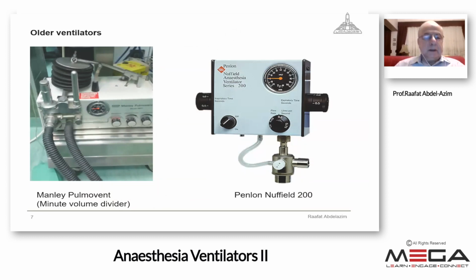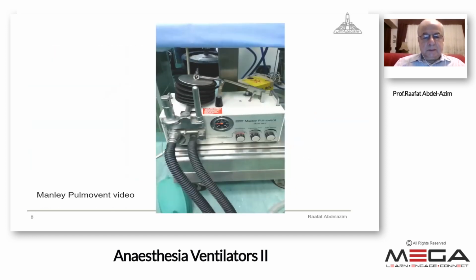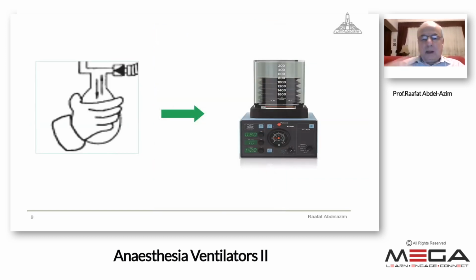In older ventilators, I already gave a hint about the older ones. I said I will summarize some important points. The first one is the ventilator replaces my hand and the reservoir bag during manually assisted or manual controlled ventilation. The power of my hand is replaced by the power of the driving gas, that is compressed oxygen under high pressure, and the reservoir bag is replaced by the bellows, which contains the patient gas inside.